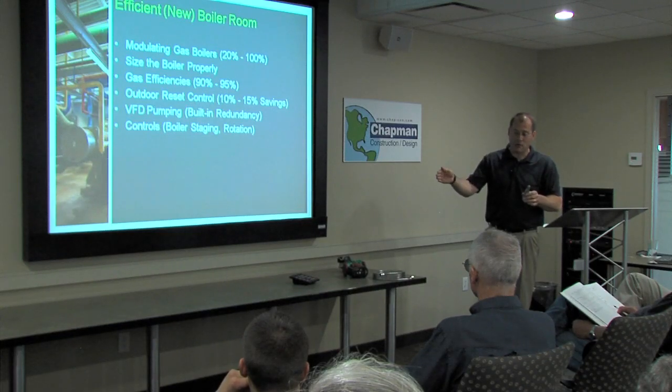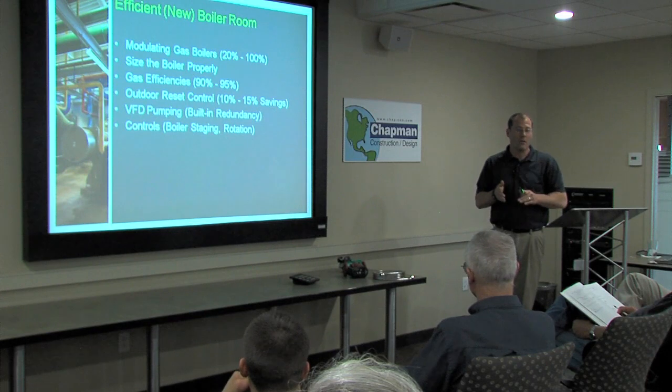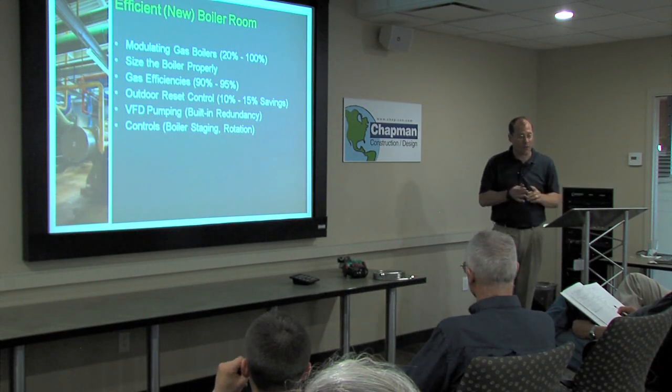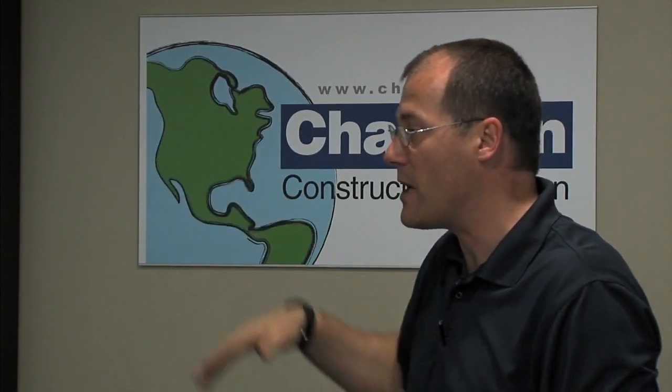you really need to understand that the colder the water in the system, the higher your efficiency. So you'll see someone claim 96, 97%. Well, it really depends on what the building is using for water temperature. If we've got a high temperature application, baseboard, radiators, fan coils, you're going to be able to have that water temperature low when it's mild out, but on the cold days it's going to be hot, and you're going to be in the 90% range.